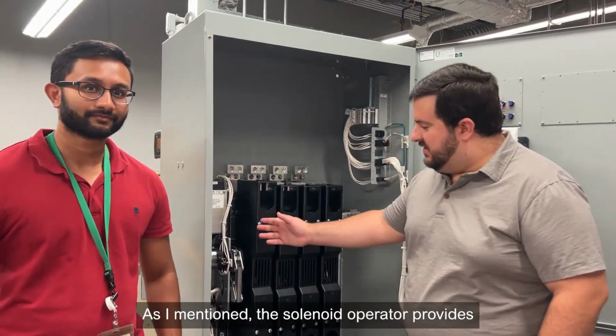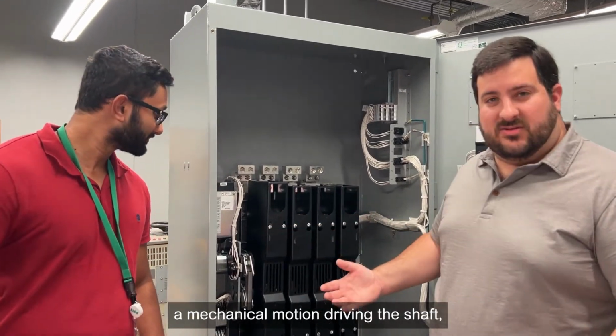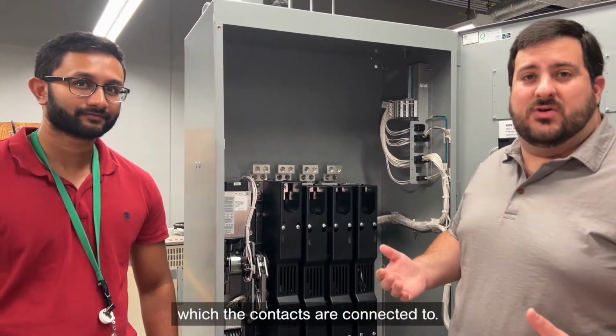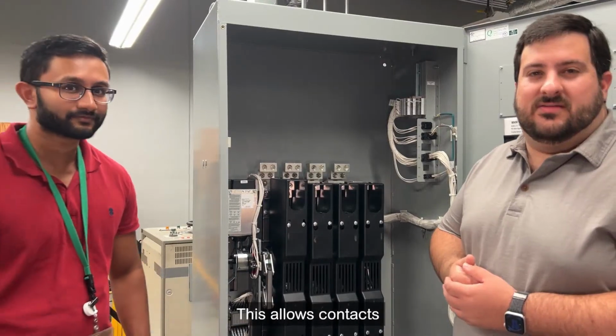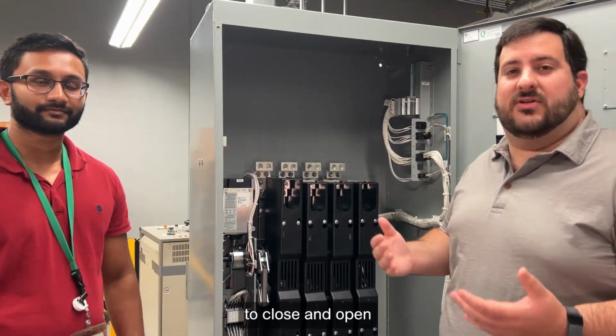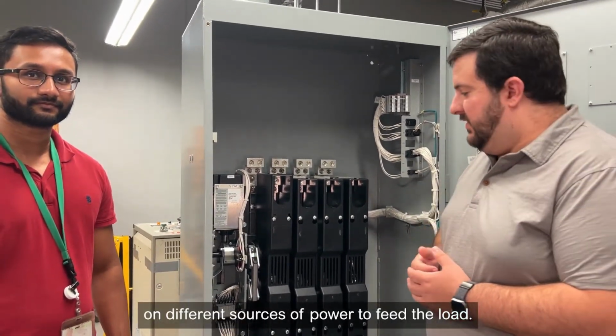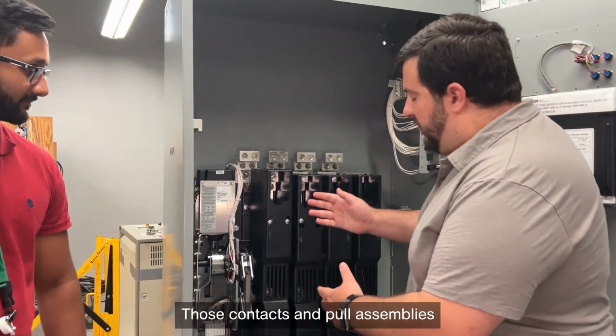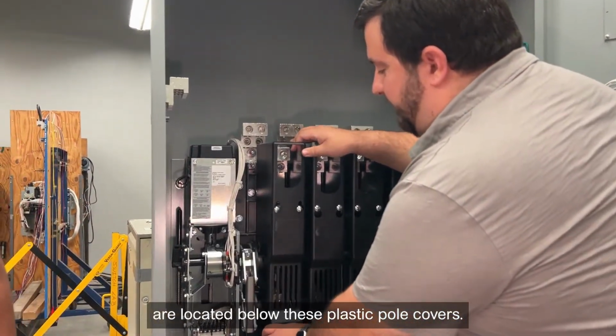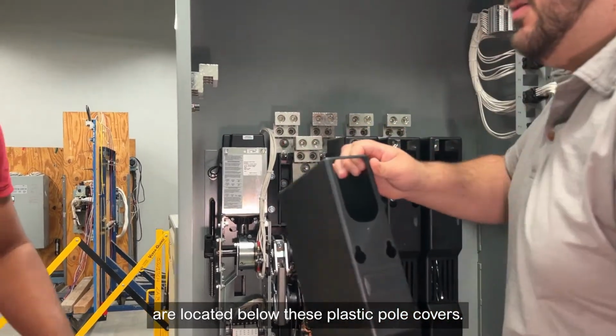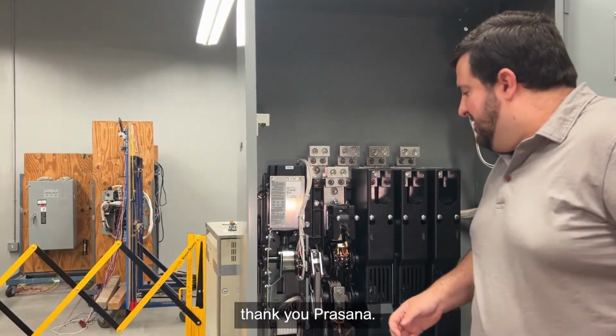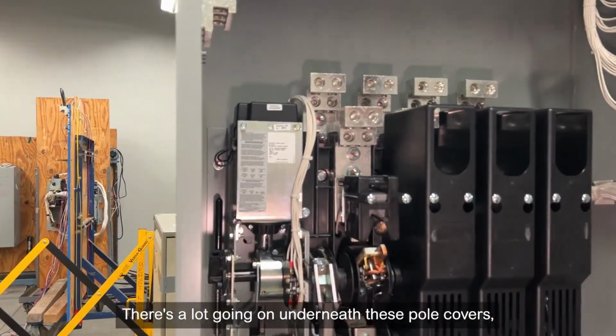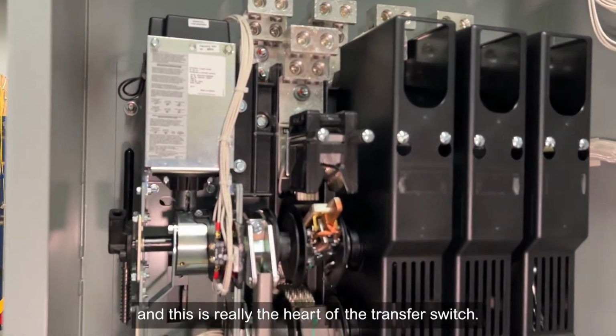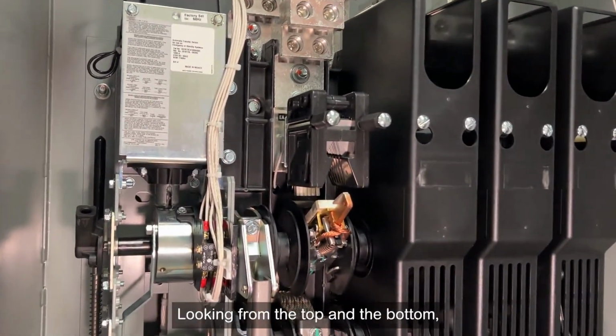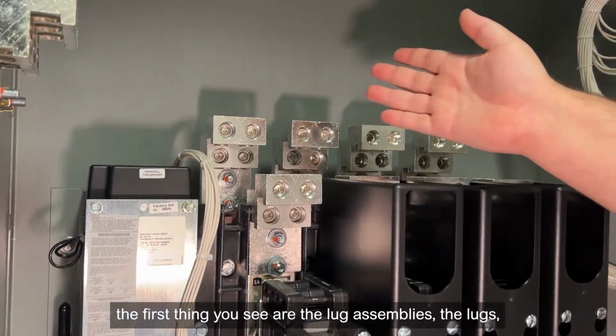As I mentioned, the solenoid operator provides the mechanical motion driving the shafts which the contacts are connected to. This allows the contacts to close and open on different sources of power to feed the load. Those contacts and pole assemblies are located below these plastic pole covers. Here you go. Thank you, Prasanna. There's a lot going on under these pole covers, and this is really the heart of the transfer switch. Looking from the top and the bottom, the first thing you see are the lug assemblies.